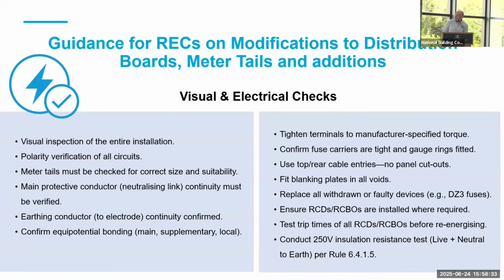So then we also conduct a 250 volt insulation resistance test. That's live and neutral, and we're testing to earth on that. So what this test does is it tests the integrity of the cables. It also lets us know if there's any existing short circuits. A most common one would be on a lighting circuit, neutral to earth.